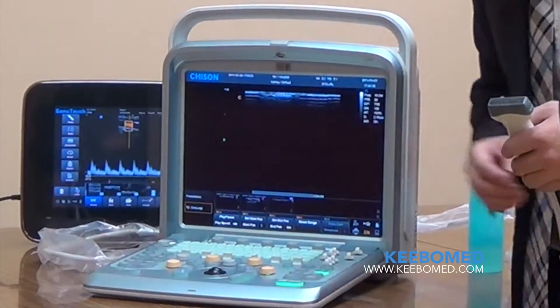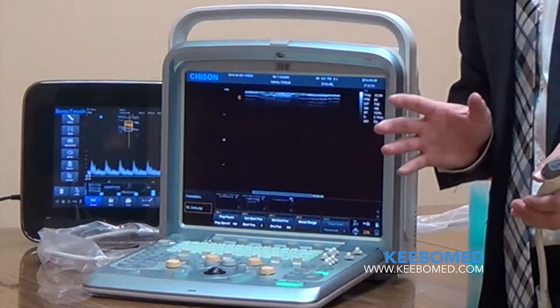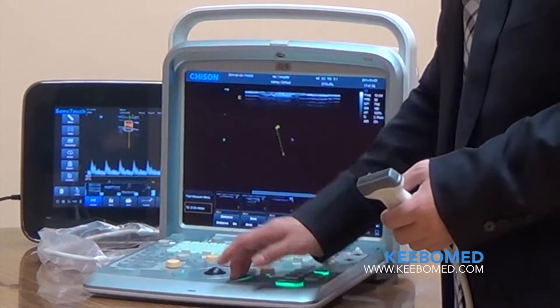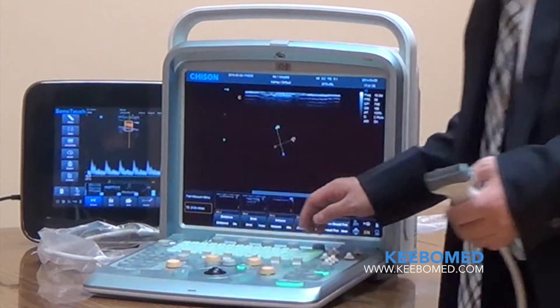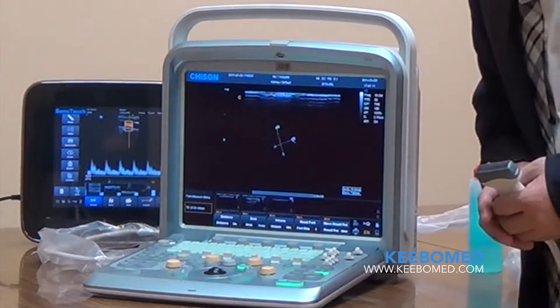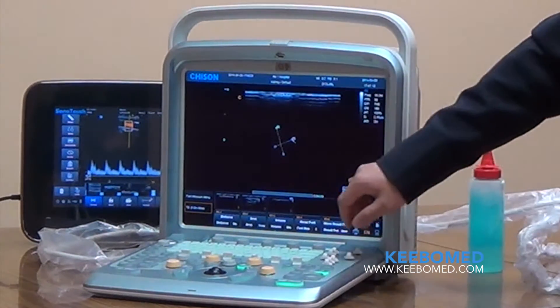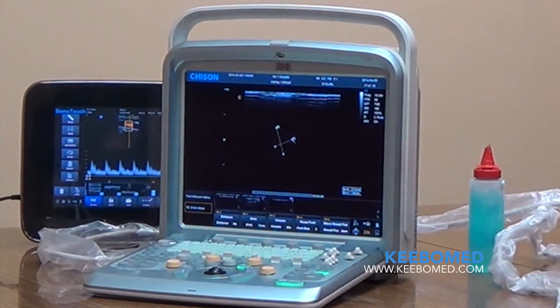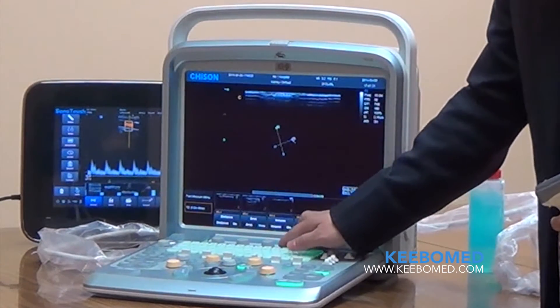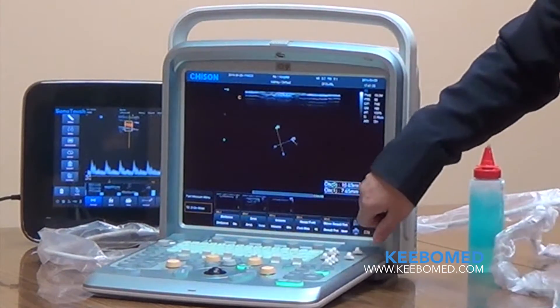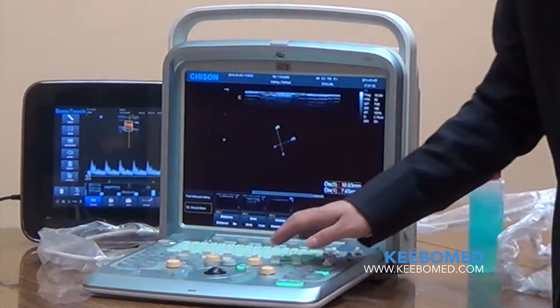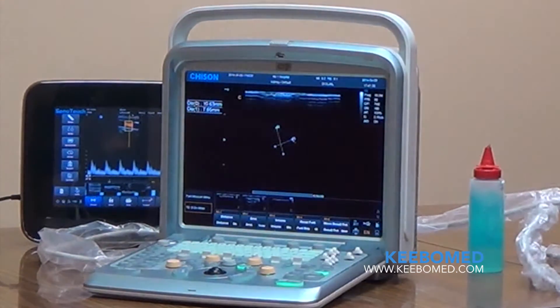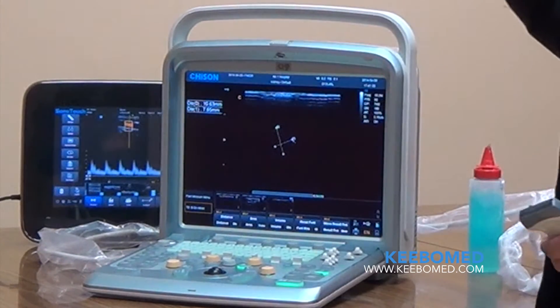When frozen, doctors often want to do measurements. For example, measuring a distance — here is the result. You may think it's too small to see from far away. On the Q5, we have a feature to adjust the font size of the result, and you can also move it anywhere on the screen.